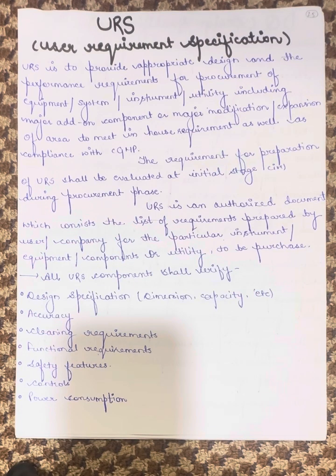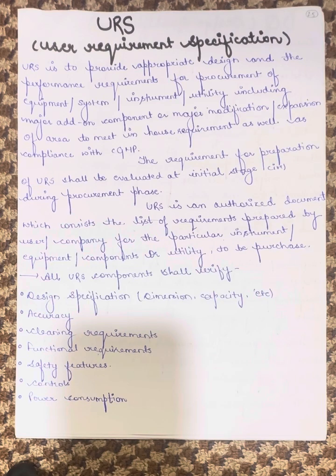All URS components shall be verified. What needs to be verified? Design specification like dimension, capacity, etc. The accuracy, the cleaning requirements, the functional requirements, safety features, controls and the power consumption.